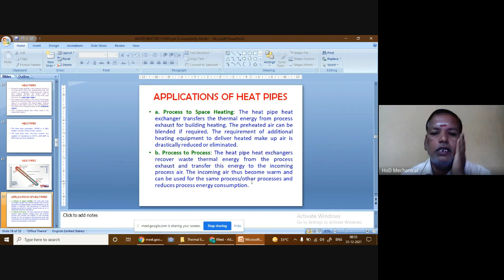The next one is process to process. The heat pipe heat exchangers take waste thermal energy from the process exhaust and transfer this energy to the incoming process air. This incoming air thus becomes warm and can be used for the same process or another process, and it reduces the process energy consumption. It is also used for HVAC applications, that is, heating, ventilating, and air conditioning applications.